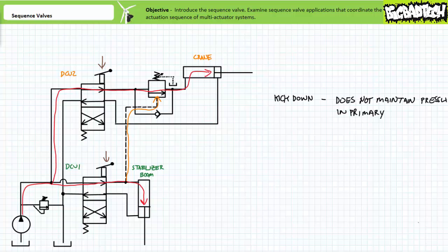Variations of sequence valves called kickdown style sequence valves exist that exhibit similar yet subtly different behavior. When a regular sequence valve shifts open, it maintains pressure in the primary circuit. Kickdown sequence valves, when shifted to the open position, shift and stay open like a regular valve, yet do not maintain pressure on the primary circuit. This could be advantageous for circuits in which efficiency is a prime consideration. While maintaining pressure in the primary circuit, there would exist a significant pressure differential across the sequence valve until pressure in the sequenced cylinder equalized. A kickdown sequence valve does not maintain pressure in the primary circuit — when actuated, it just opens up and stays open, and pressure in the whole system drops to whatever it took to actuate the sequenced actuator.